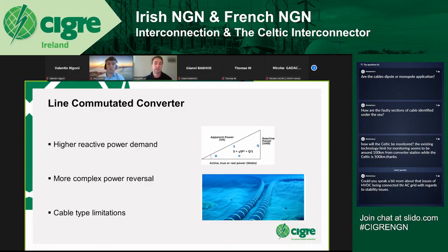With VSC, power reversal is much more instantaneous and easier. Because of this, LCC has a reduced selection of cable types, typically using mass impregnated cables, which are chunkier. Whereas with VSC, we're able to use XLPE extruded cables, which are more common in the network at the moment.